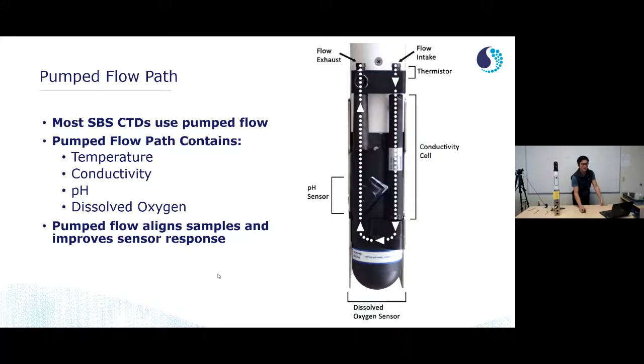So the pH module, this is one of the more special things about the HydroCAT EP family, and we've redesigned the pH module for the HydroCAT EP V2. As mentioned before, this is a modular field swappable sensor. You can calibrate it in the field or in the lab if you have multiples of these. That being said, because it is a glass electrode sensor, it has to be stored in potassium chloride in this soaker block. So what you can do is calibrate this in the lab, store it in the soaker block, take it out to the field, and install it in your HydroCAT EP that's currently deployed.